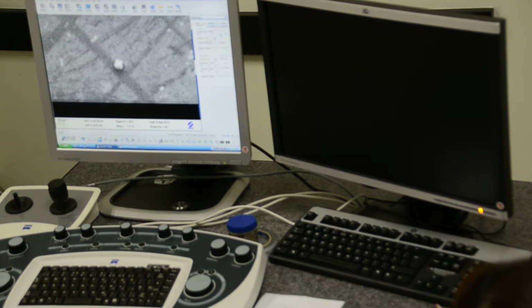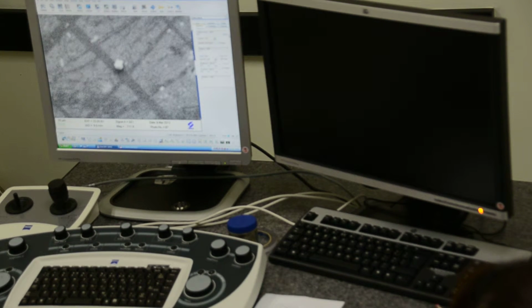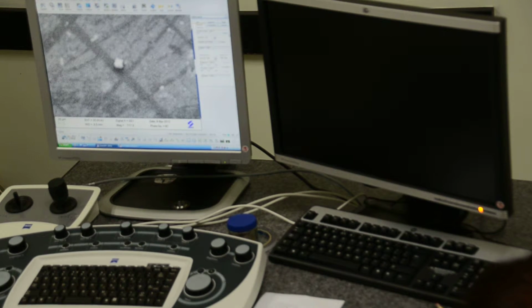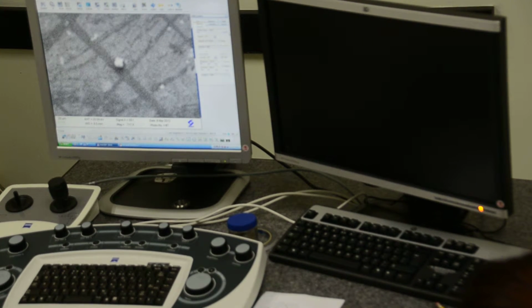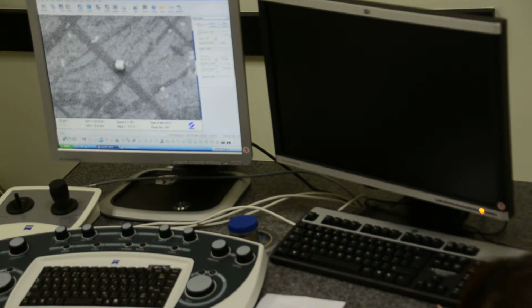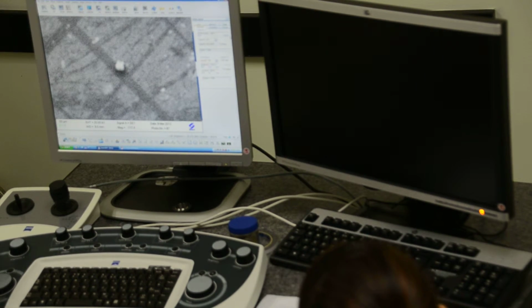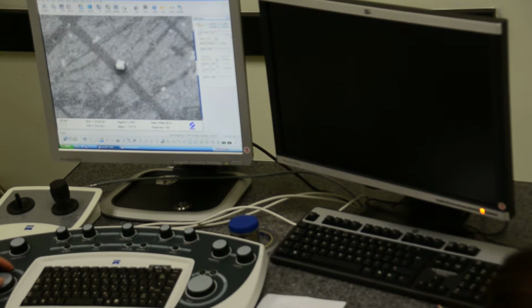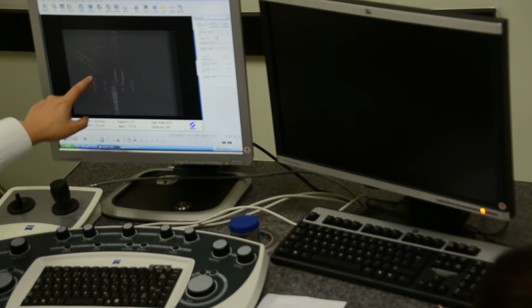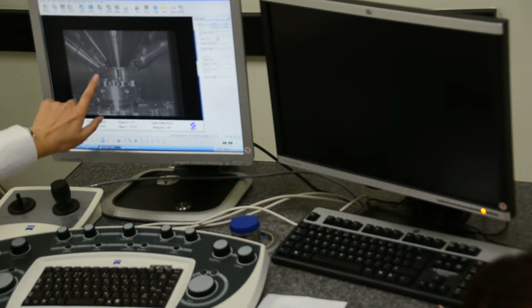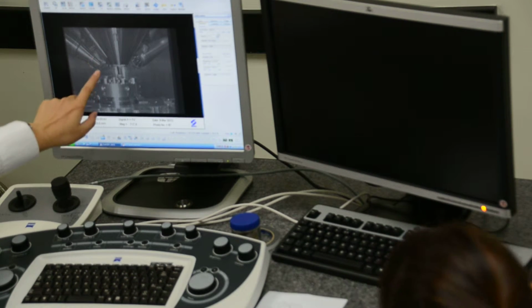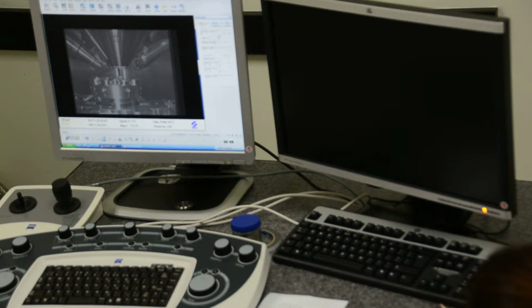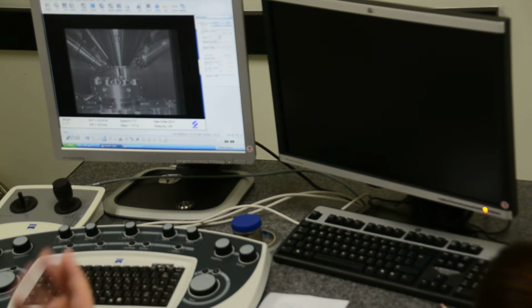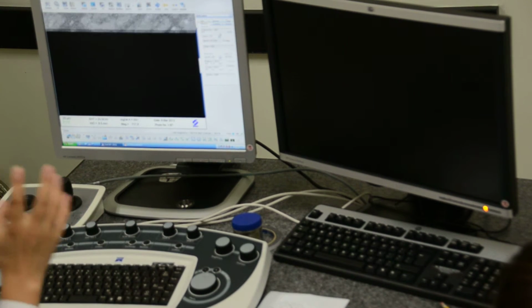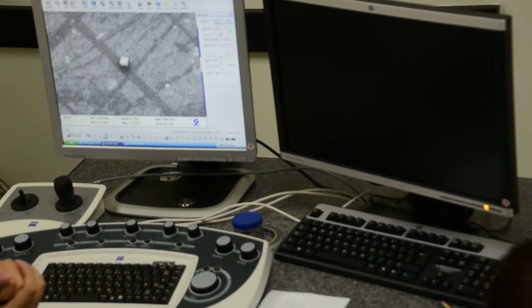My range can apply as high as 400. So applying a larger value, you can trap more electrons. You may get a slightly better signal to noise ratio. This is the collector bias value, which changes the bias voltage of this cage, so it's pulling the electrons towards it. So you set the value. We are setting about 300 to 400.